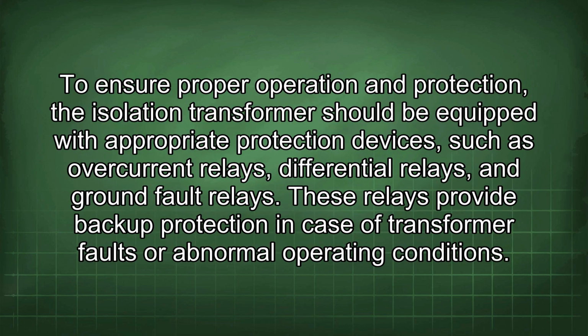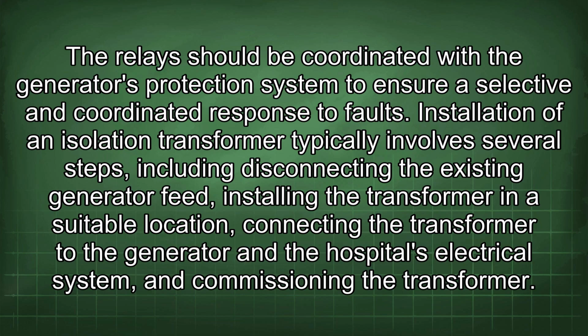To ensure proper operation and protection, the isolation transformer should be equipped with appropriate protection devices, such as overcurrent relays, differential relays, and ground fault relays. These relays provide backup protection in case of transformer faults or abnormal operating conditions. The relays should be coordinated with the generator's protection system to ensure a selective and coordinated response to faults.